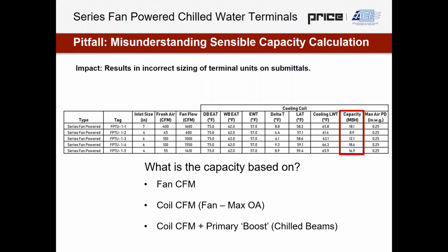Sometimes when you go through and try to pick out and do some hand calculations to garner some more understanding on the schedule, sometimes I see this capacity is based on a fan CFM running through the coil, which is unrealistic. Sometimes you see that this max cooling coil capacity is a coil CFM, so a fan CFM minus an outdoor air maximum CFM, which we'll look at in the next slide. And then sometimes we see that this would be a coil CFM and then also a primary sensible boost. So for those familiar with chilled beam systems, this would be a chilled beam type sensible capacity.